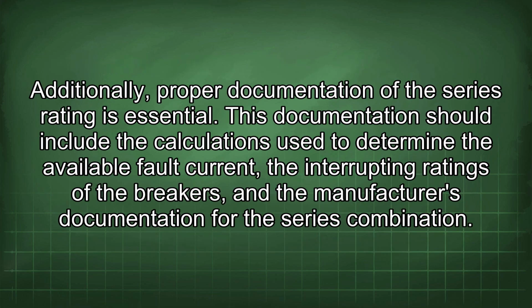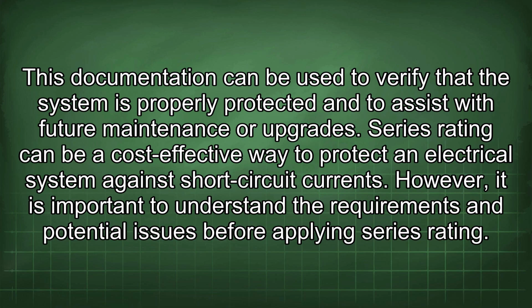Additionally, proper documentation of the series rating is essential. This documentation should include the calculations used to determine the available fault current, the interrupting ratings of the breakers, and the manufacturer's documentation for the series combination. This documentation can be used to verify that the system is properly protected and to assist with future maintenance or upgrades.